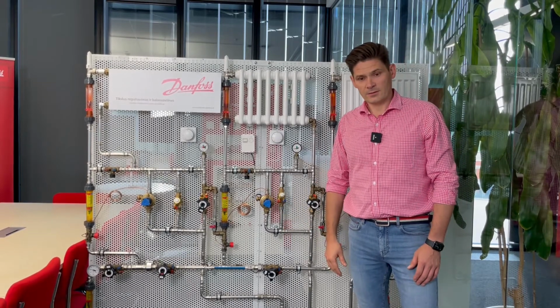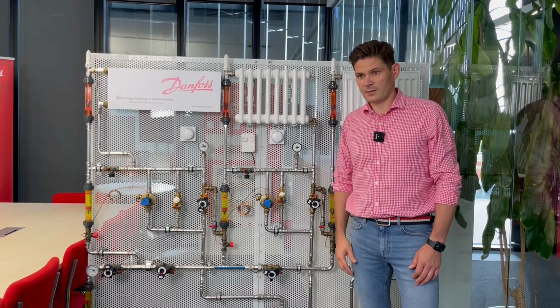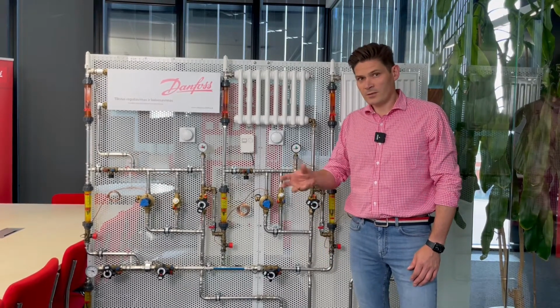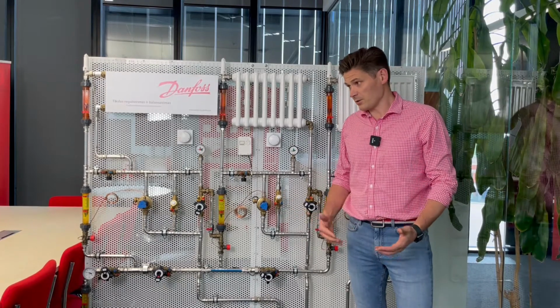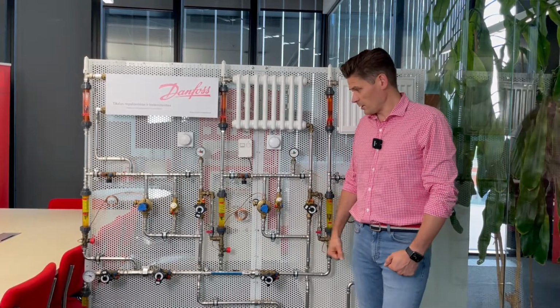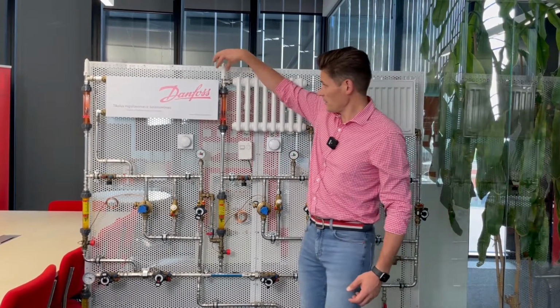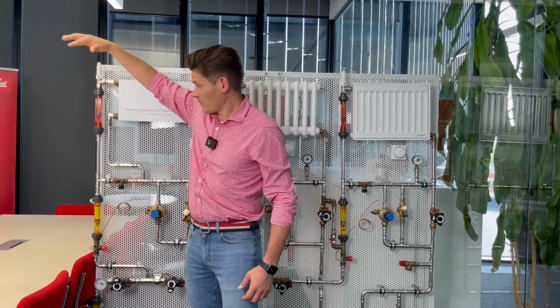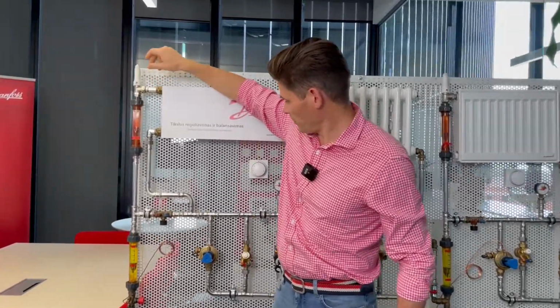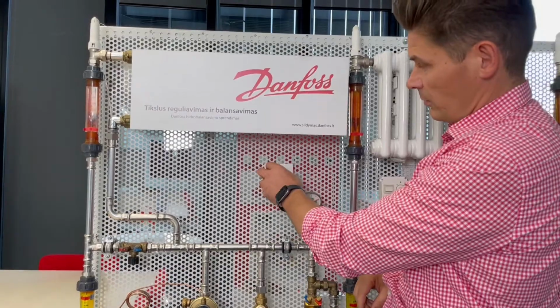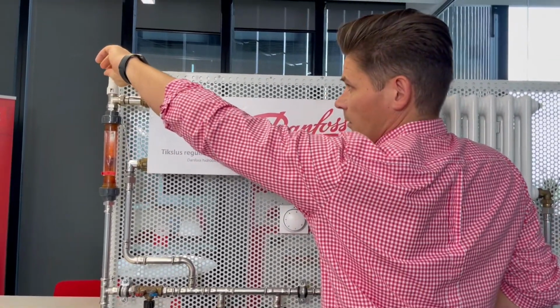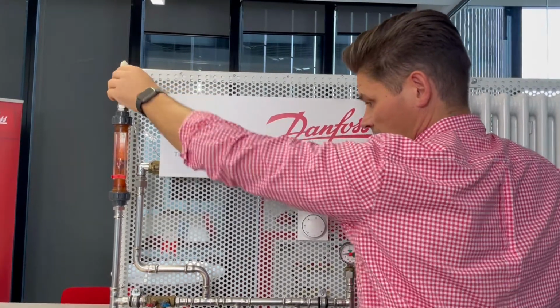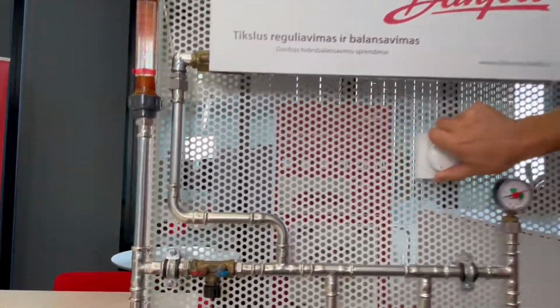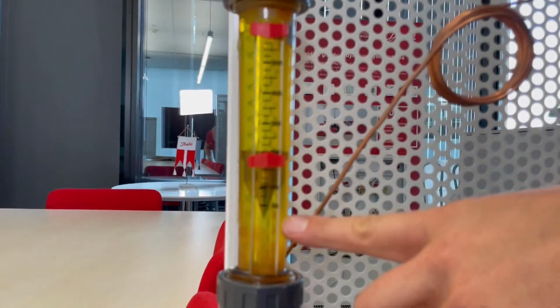After the heating season, tenants get an idea that maybe they would like to regulate radiators. Maybe they would like to put something on the radiator and have the possibility for regulation of flat temperature, of each room temperature. So they collect money, here comes the installation company, and they put thermostats here on radiators. Here we have already put remote regulation. Here is the impulse tube, and the thermostat is right here. So I regulate here, and the thermostat closes the valve using this impulse tube. So, for example, if I close, you can see the flow is shutting off. If I open, it opens again.